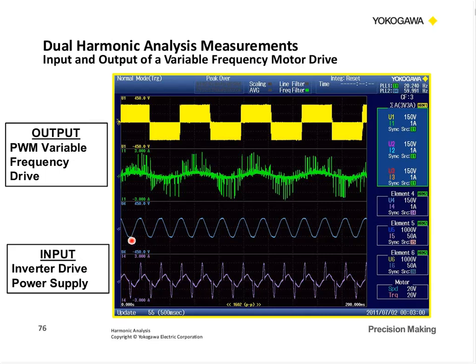So we've got a clean sine wave input before it's all chopped up. This is the power supply current input that's pulsed. It turns on at the peak of the voltage, so we get that peak, pulse current. A lot of difference between the two of them. So we can look simultaneously between these two waveforms.